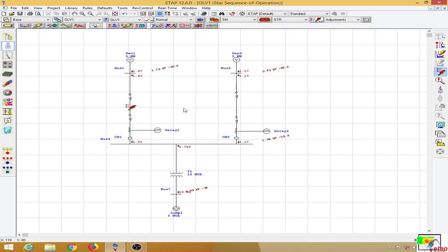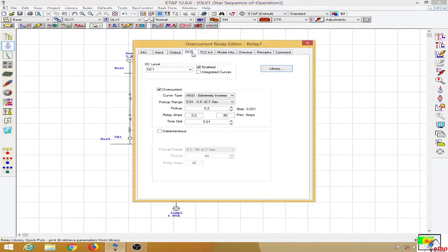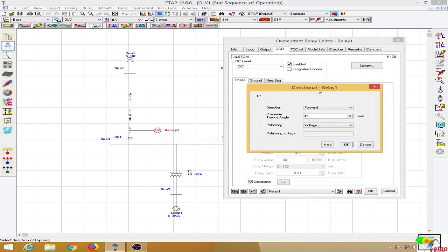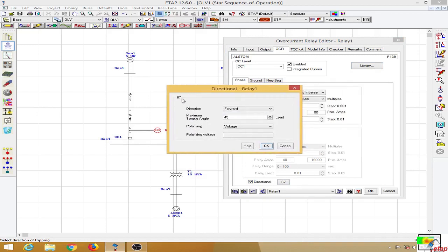Let us see how we can implement the directional relay. Double-clicking on the relay and going to the overcurrent page, I have used the Alstom P139, which already has the directional element available. I tick on this portion and click on device number 67 — the device number for the directional relay. The direction is set to forward, which I will explain in a moment.